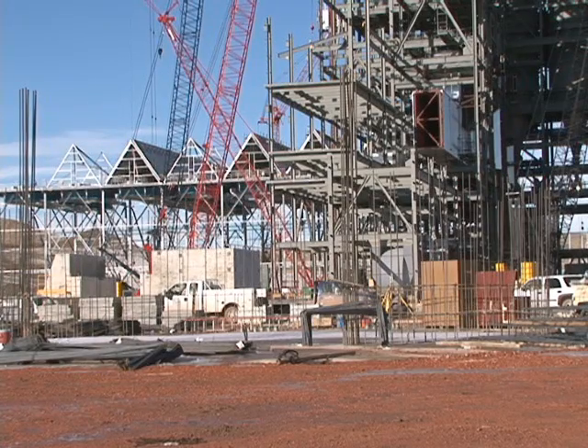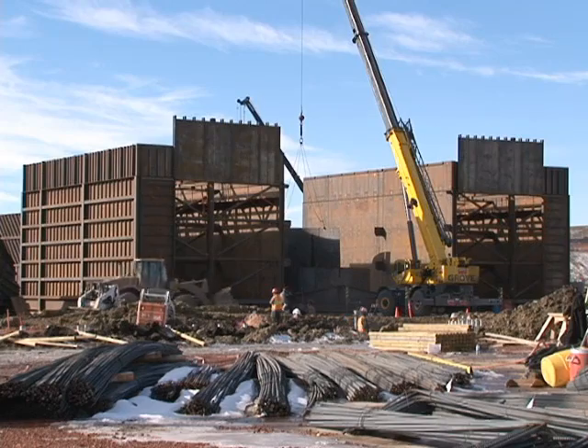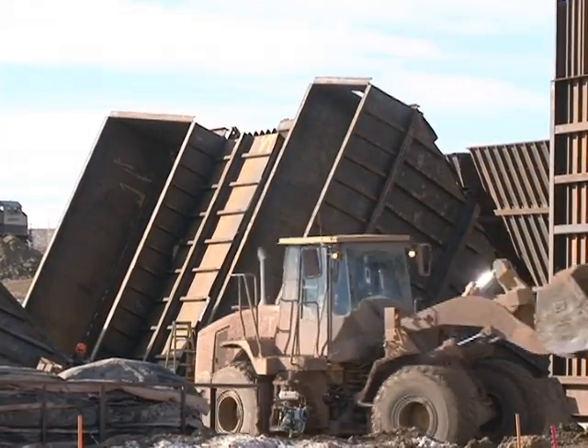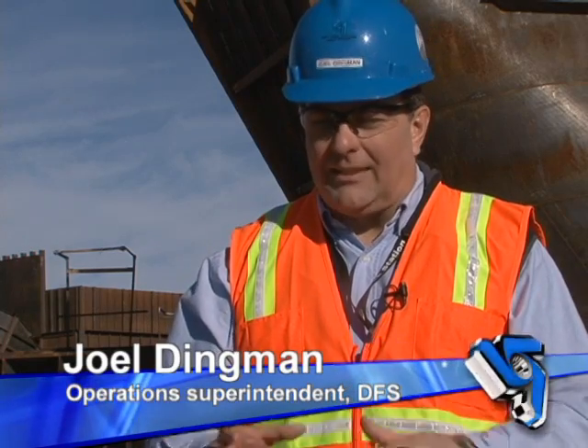The flue gas contains ash and a little bit of lime, which is pulled to the bag house. These are the bag house compartments — it works like a huge vacuum cleaner. When the bags are shaken to release the ash and lime, it falls into hoppers and is sent back to the scrubber vessel. The product is recirculated to ensure maximum efficiency, with the goal of using as high a percentage of the lime as possible so that it's all inert when it becomes a waste product.